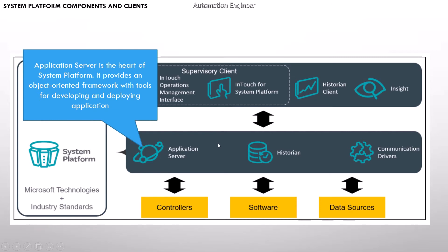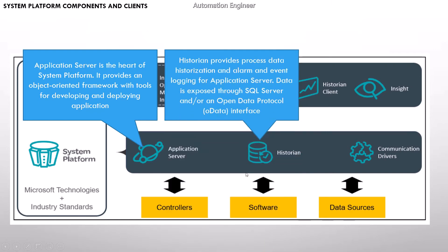Now we come to the second layer: the system platform components. First, we talk about the Application Server. The Application Server is the heart of the system platform — it provides an object-oriented framework with tools for developing and deploying applications. The second component is the Historian. The Historian provides process data historization and alarm and events logging for the Application Server. The data is exposed through SQL Server or an Open Data Protocol OData interface.